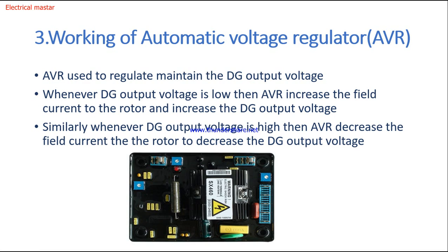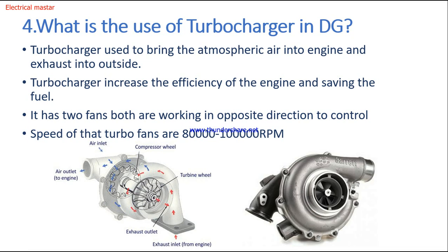Third question: how does the AVR — automatic voltage regulator — work? The AVR is used to regulate and maintain the DG output voltage at the rated value. Whenever the DG output voltage is low, the AVR increases the field current through the rotor to increase the output voltage. Similarly, when the output voltage is high, the AVR decreases the field current. If you want more detail about the AVR, click the info button — I have a separate video explaining how the AVR works and how to connect it with the diesel generator.